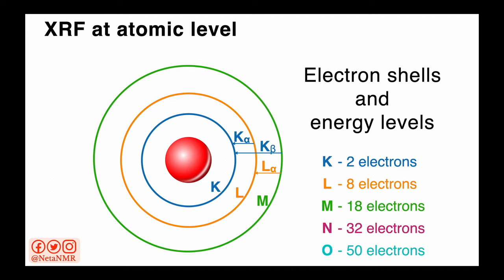Why is this important? It's because the X-ray fluorescence associated with each of these transitions has a precise energy value. This energy is given by the energy difference between the inner shell and the outer shell. And in this example, if we're looking at the K-beta transition, the energy of the X-ray fluorescence is given by the energy between the K-shell and the M-shell. This is very important because these energies are specific to each element. They're like fingerprints for the elements. Once we know the values of these energies recorded by the detector, we can identify the elements that are present in the sample.